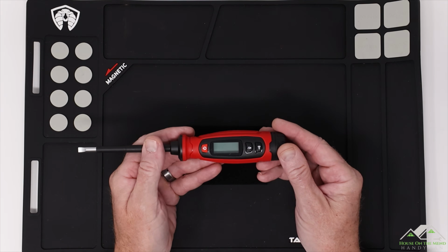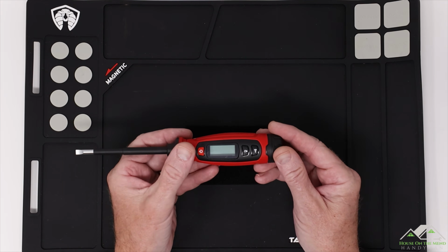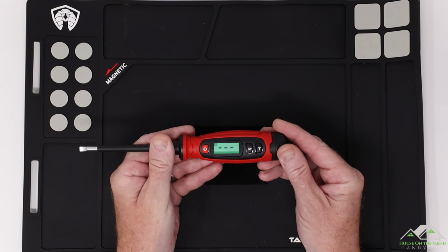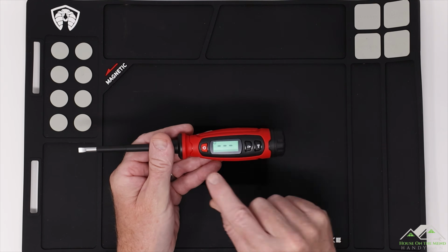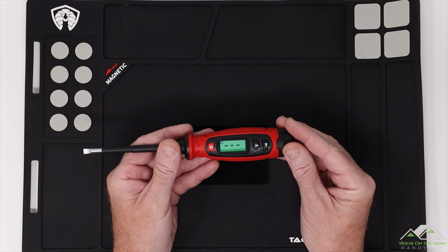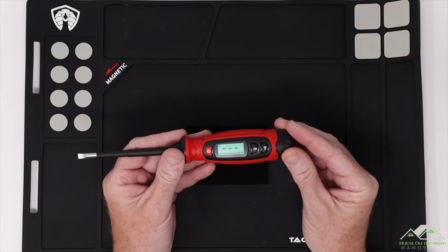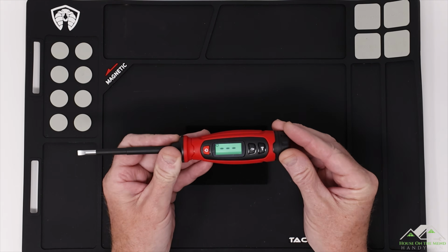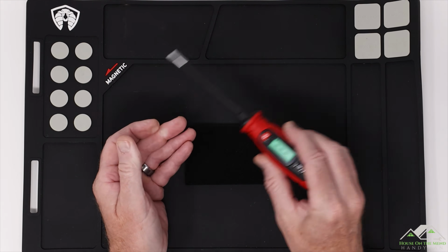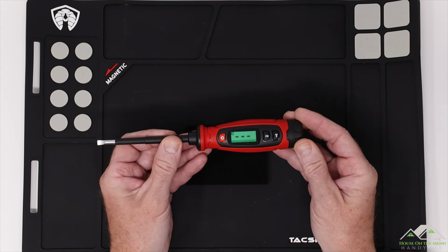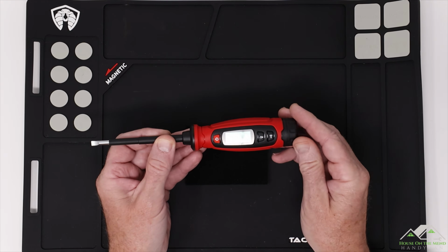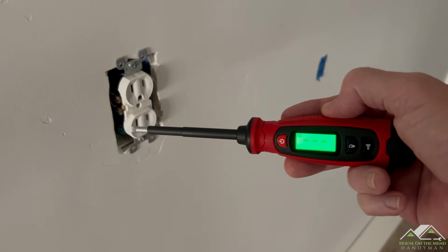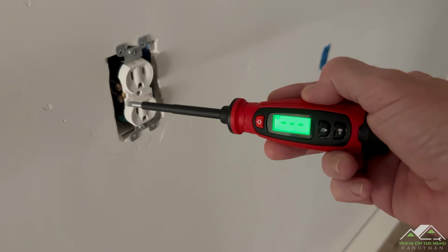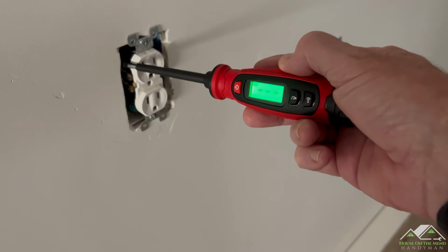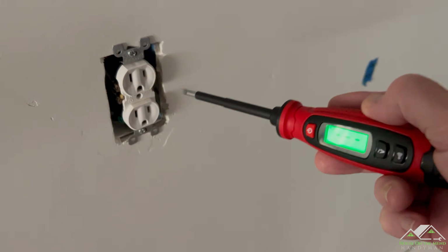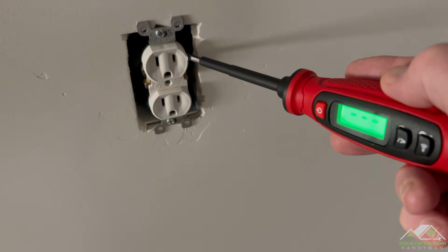All right, let's go over the functionality. First of all, to turn on the tester, you press and hold the power button for 1 second. Green light comes on. If you see the 3 dashes, that's because by default, it starts off in non-contact voltage mode, basically going around and sensing for electricity. Namely, it's looking for AC power. Now, when coming up to a live outlet on the neutral side, the tool is not concerned at all. It's only when you get over to the hot side that it starts to alert you.